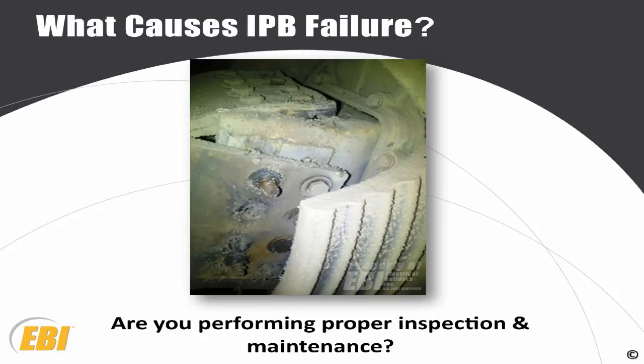This is showing a seal-off bushing that's had a failure where it blew the bushing apart. Notice all the residue on this. That's the carbon and ionization where a failure happens.